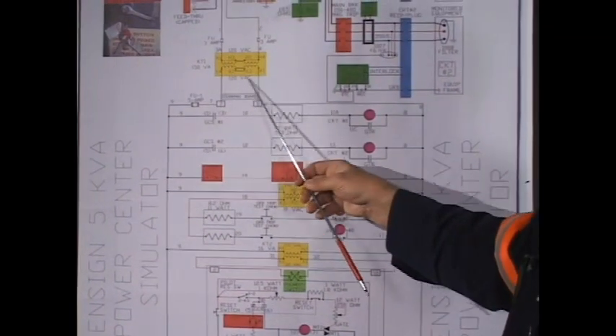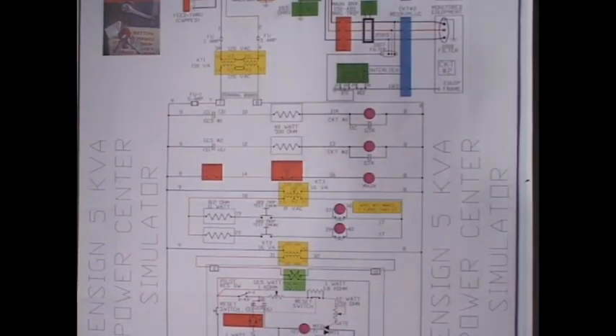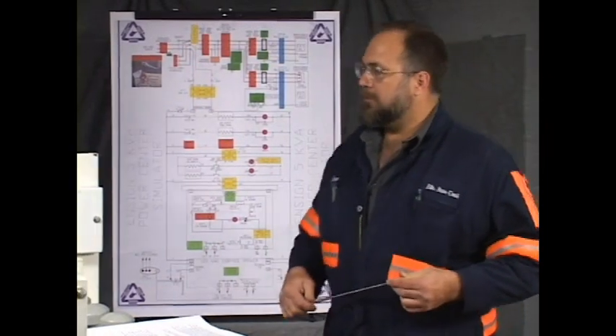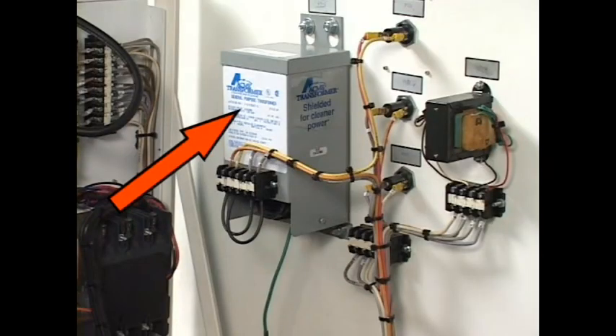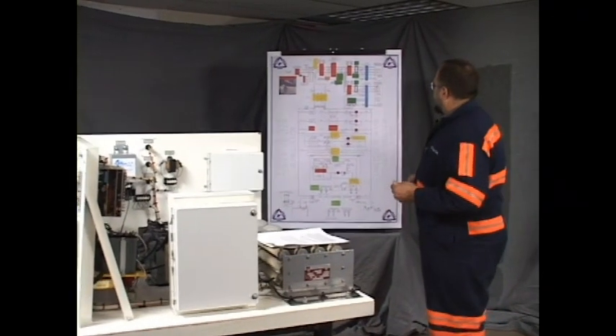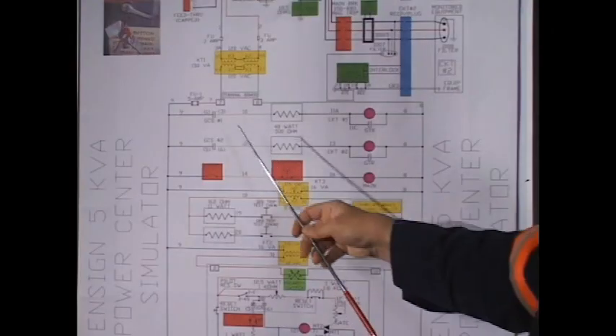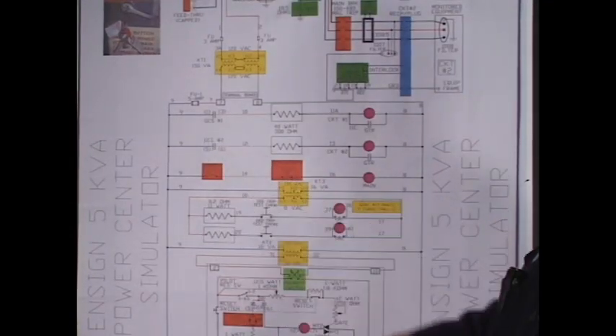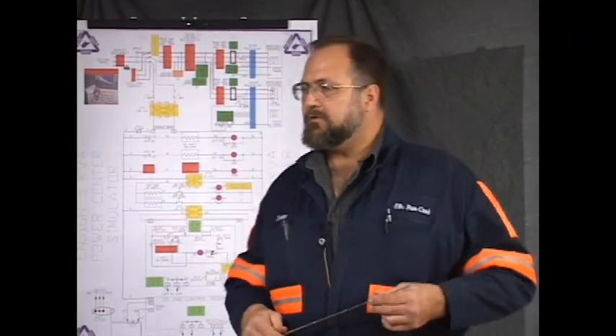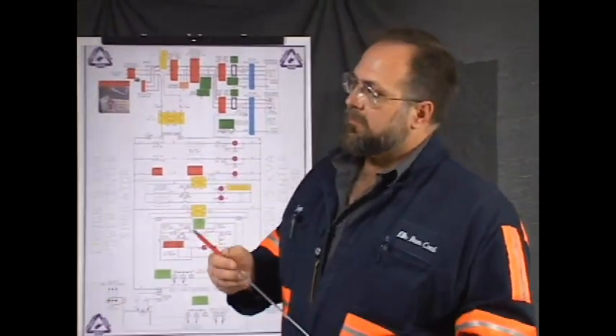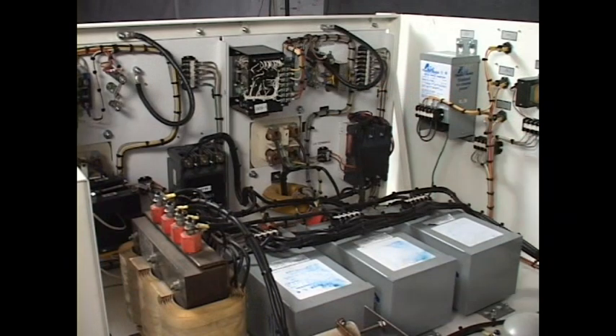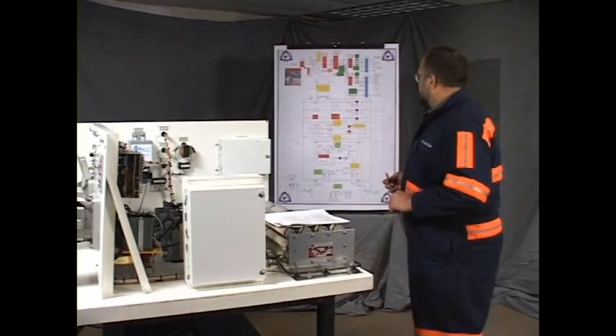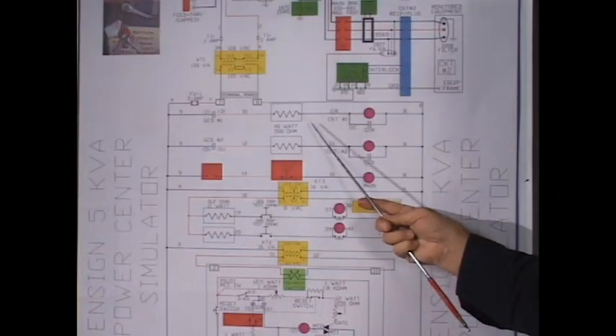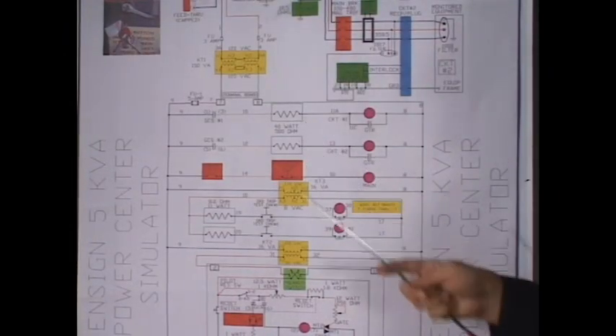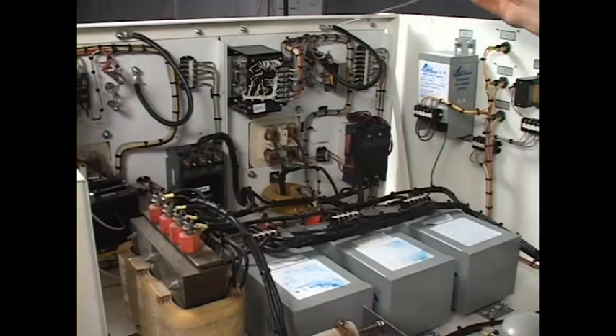The first one would be the KT1. That's a transformer. That's a real popular symbol on many drawings. KT1 on the actual unit is this component here. Next you have GCS1. There's a contact GCS1. It's actually part of a larger system, and that contact is located inside this component here on a little ice cube relay. We have a 40 watt 500 ohm resistor on that print, and that 40 watt 500 ohm resistor is right here.